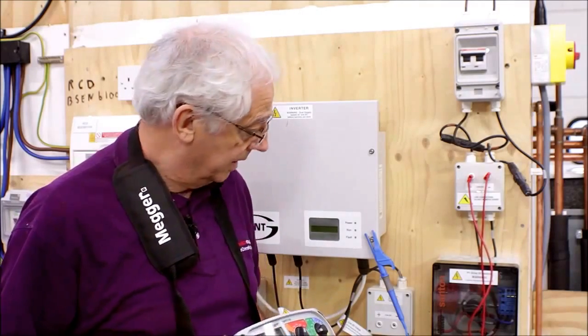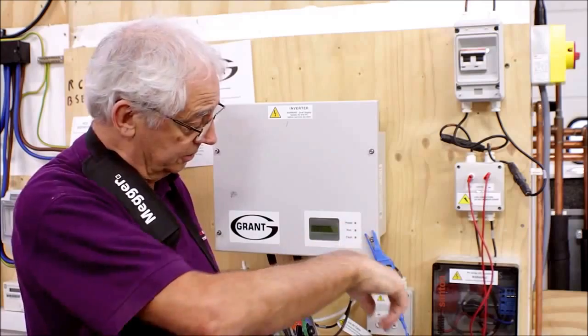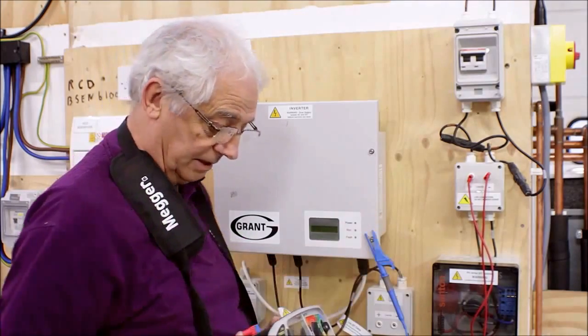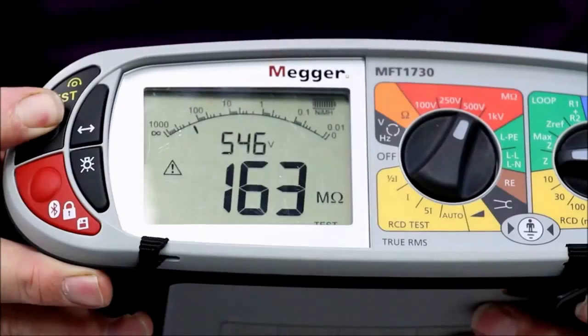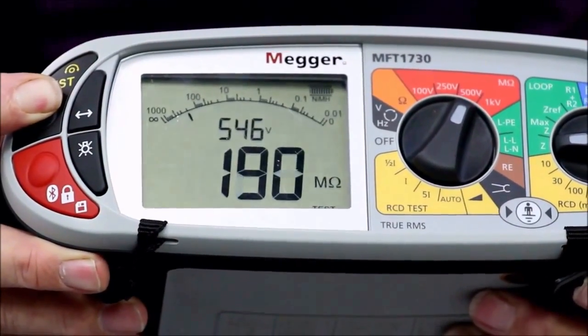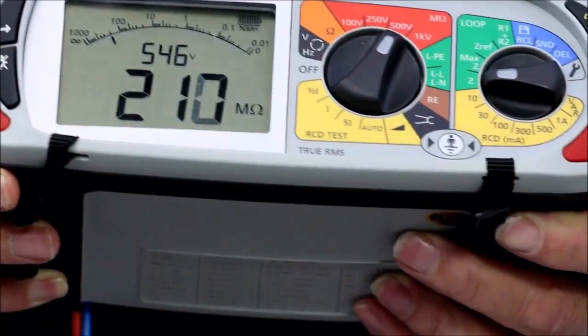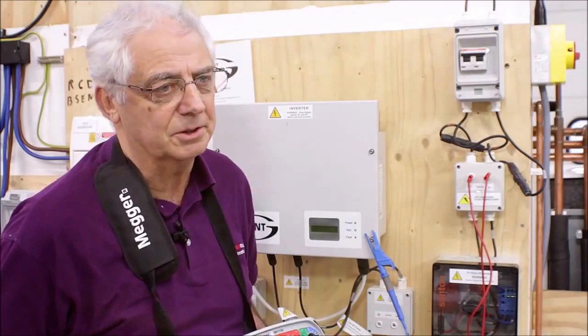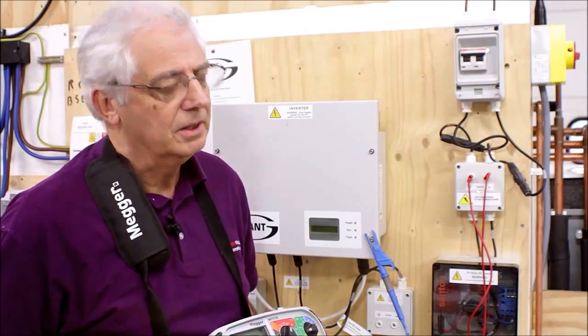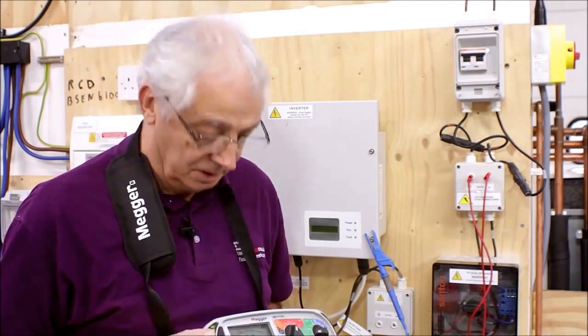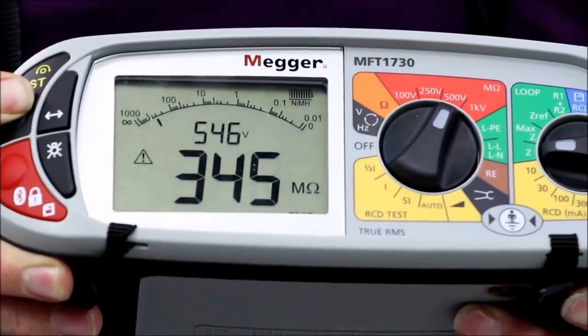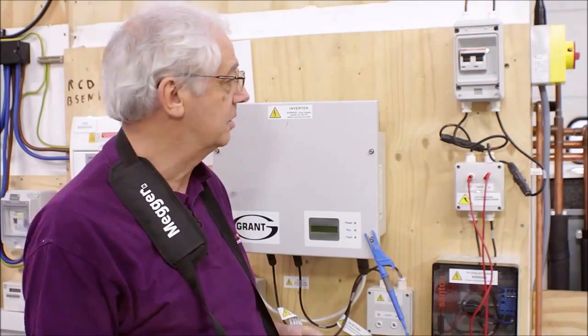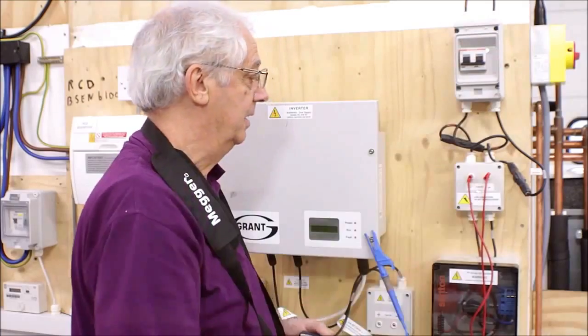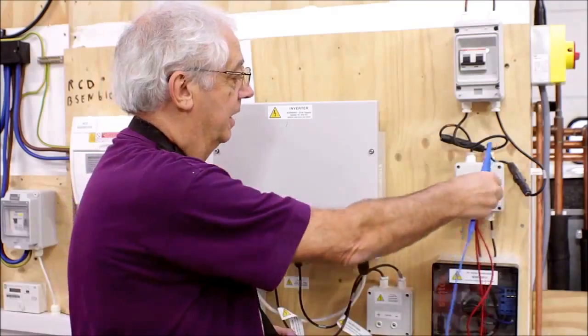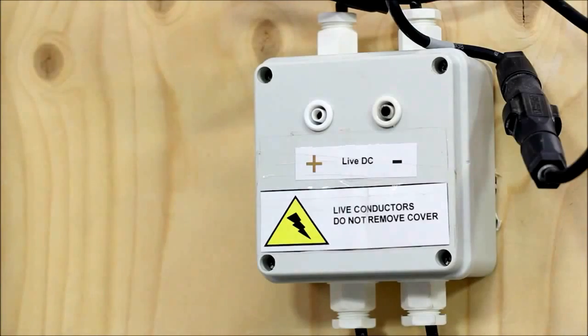I now take a value of resistance, insulation resistance between this contact and the known earth, push the button, and you can see that I've got a reasonably high reading there. It's 200 megohms and creeping up, and it will continue to creep up until it reaches a very high level. So at this point, we know that that's quite a safe installation as far as insulation values goes. Important to remember before I touch anything at all, turn off the isolator, and then at that point I can disconnect all of my connections.